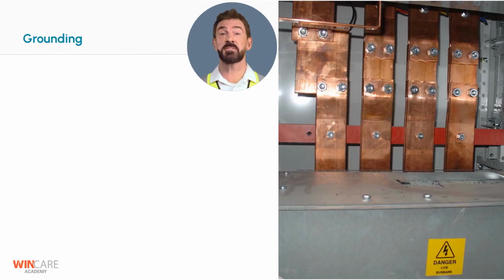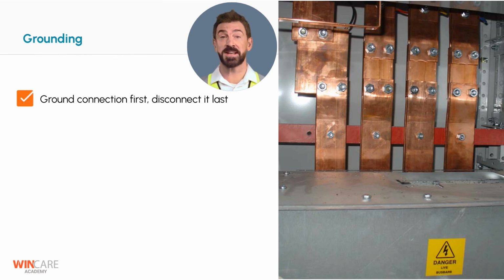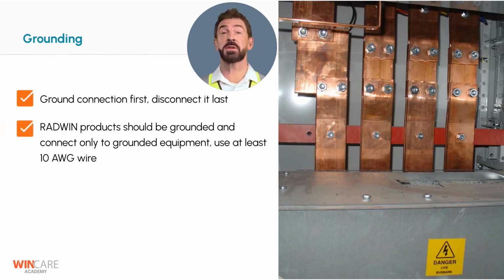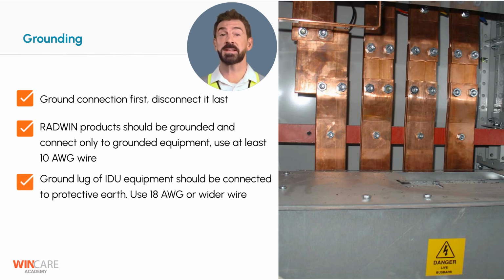Grounding is a critical safety requirement for all RADWIN installations. Always connect the ground first and disconnect it last. RADWIN products must be grounded and connected only to properly grounded equipment. Use a grounding wire of at least 10 AWG for outdoor units and ensure the ground lug of indoor equipment is connected to protective earth using an 18 AWG or wider wire.